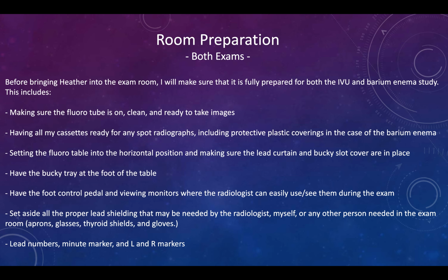And I'll have the fluoro table set into the horizontal position, make sure the lead curtain and Bucky slot cover are in place, have the Bucky tray at the foot of the table, and just have everything set up nicely for the radiologist, have that foot control pedal and the viewing monitors right where they need them during the exam.